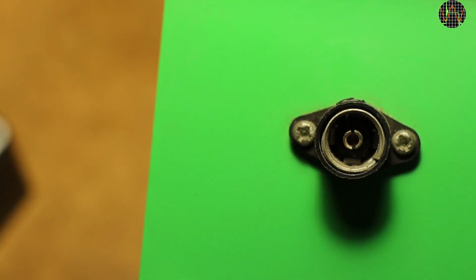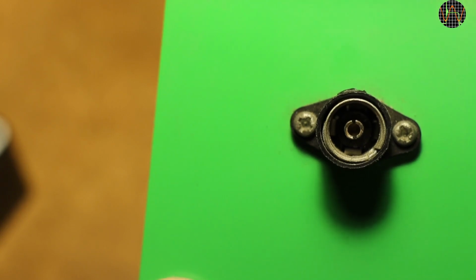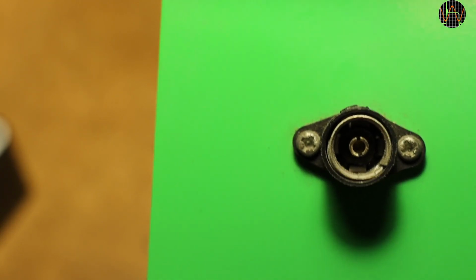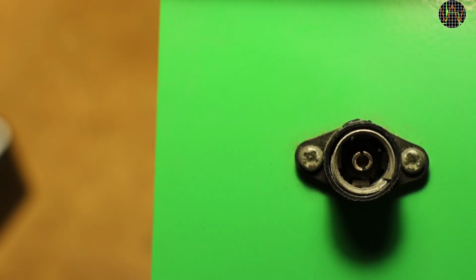The front panel socket is not designed for higher voltages, but you could touch the conductor easily if no mating connector was plugged in. I guess that's what the 1 megohm resistor is for. At 1000 volts, that would limit the current to a non-lethal 1 milliamp.